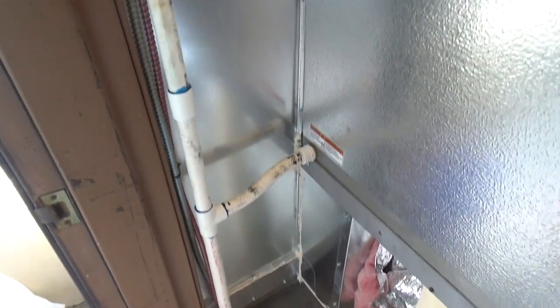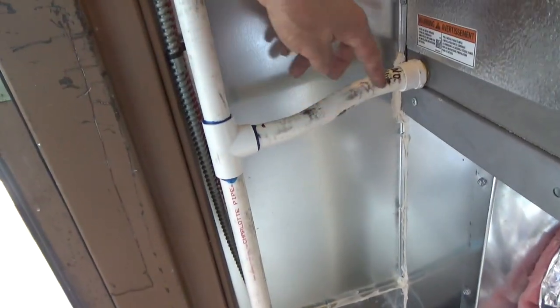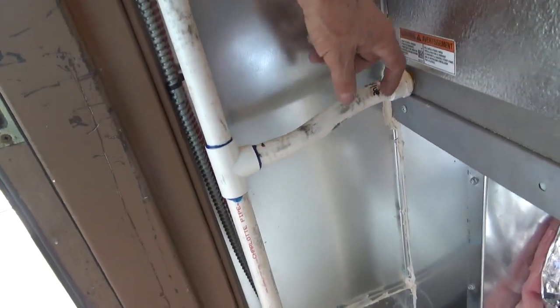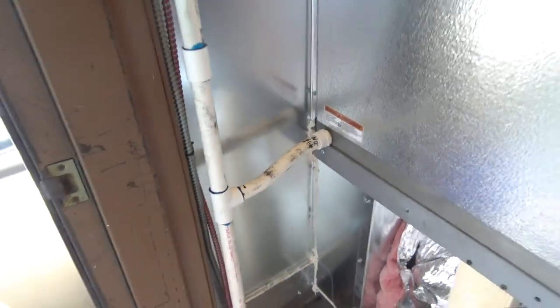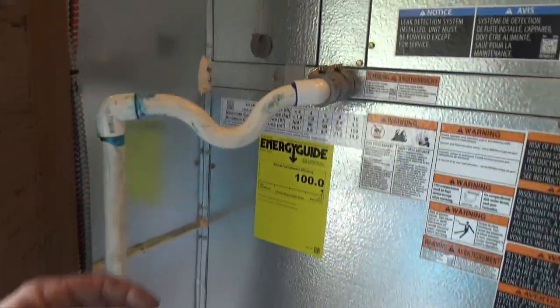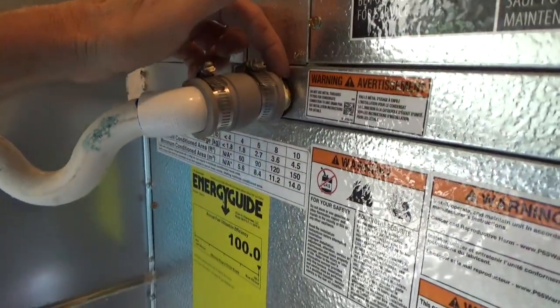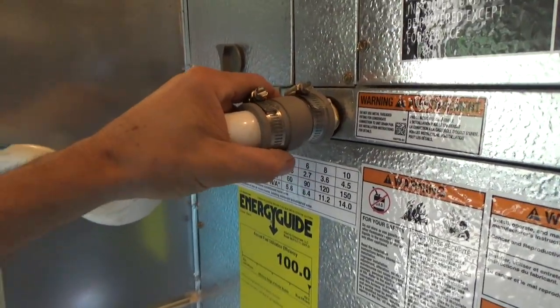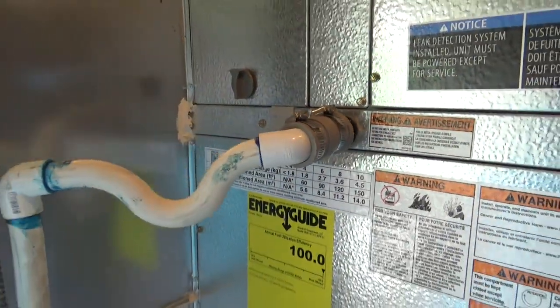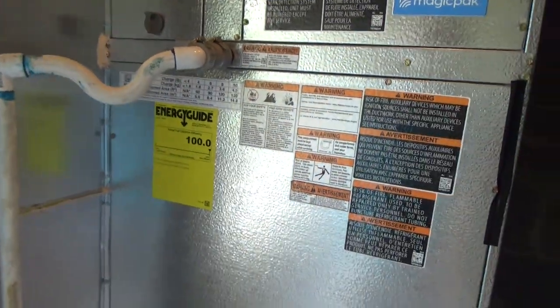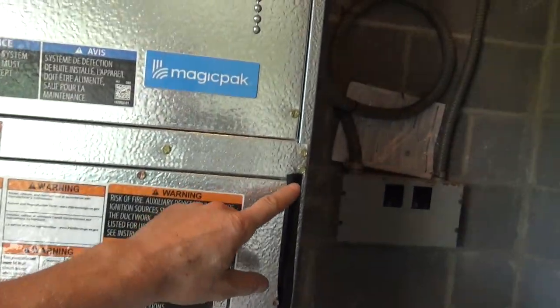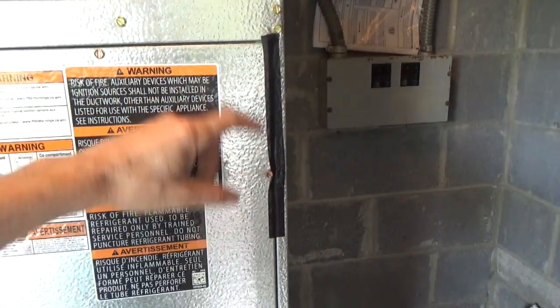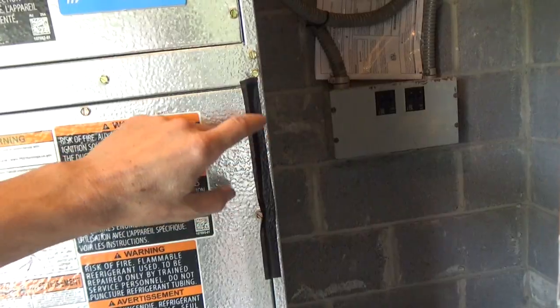Drain, since it's top floor. We got a little bit of slope here, so I can't dump water into the pan. These break real easy, so it's nice to have some rubber on there. It's not gonna break the drain pan. Seal the air leaks. Piece of electrical tape. That'll actually stay there 20 years.